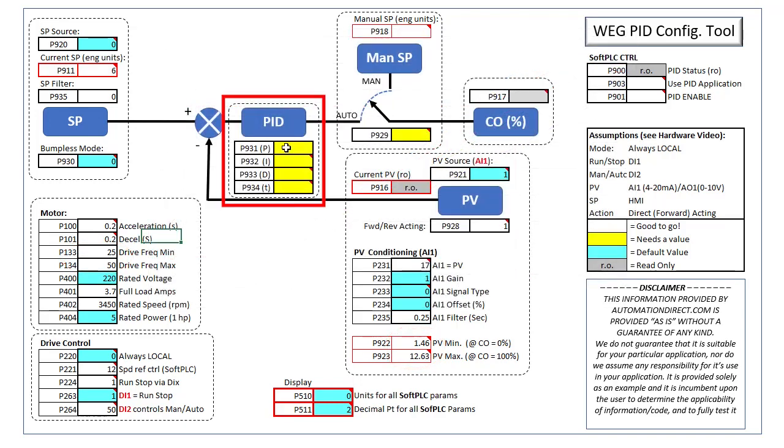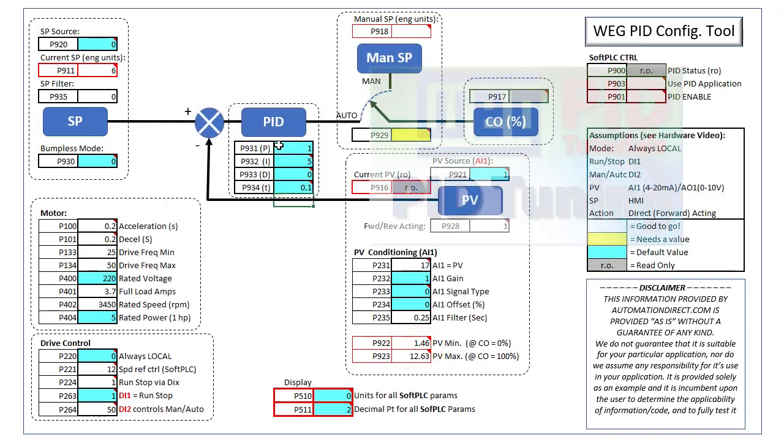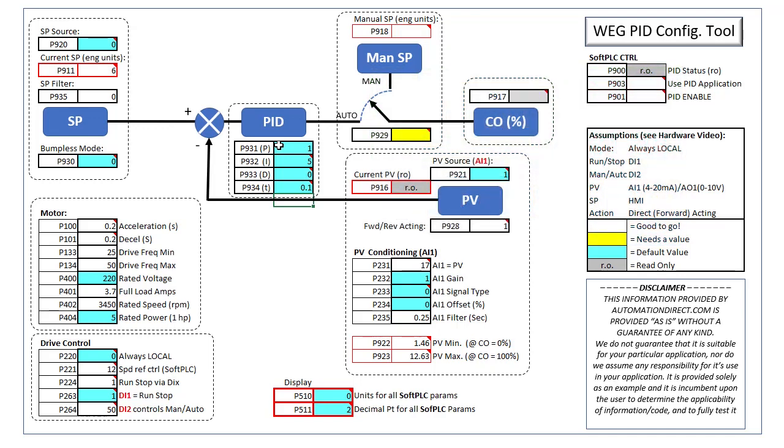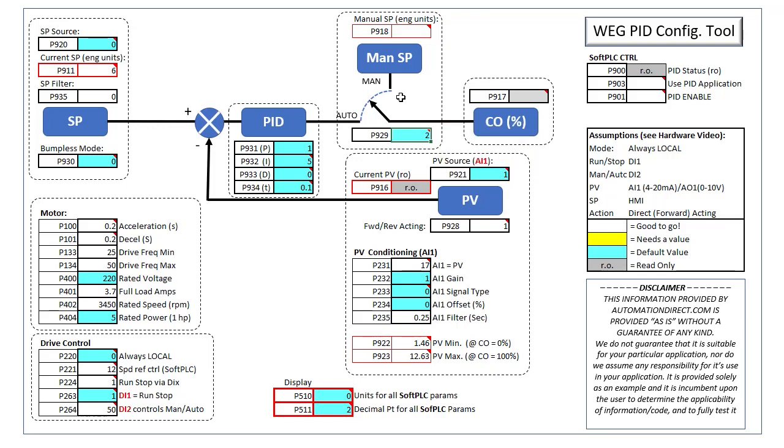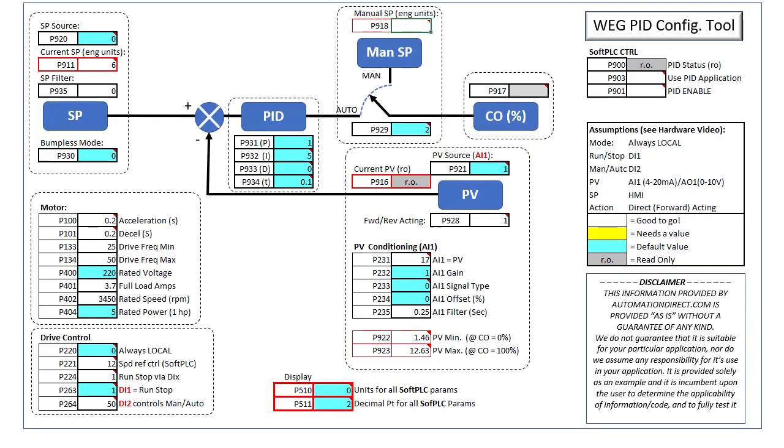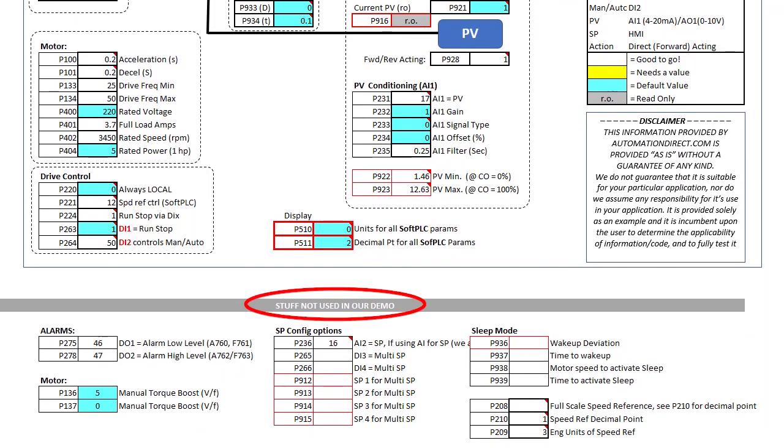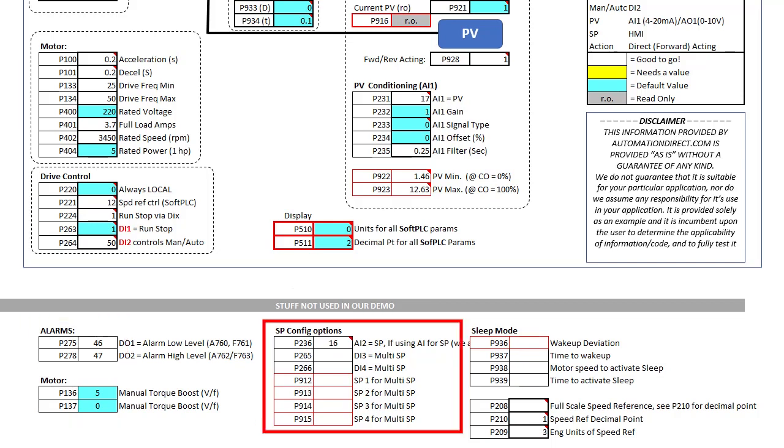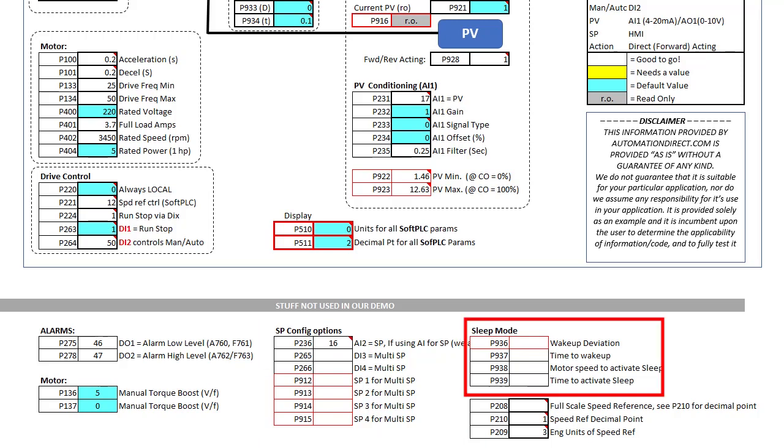Our initial PID values are easy. We just use the default values. The PID tuning video will give you a better feel for what each actually does and how to optimize them. We are going to control the manual auto modes from digital input 2 and this is where we put the value we want for the drive's output. Down here I listed the parameters we didn't use for this demo just so you have them available if you want to use alarms or add torque boost or use a different type of set point or if you want to use sleep mode.